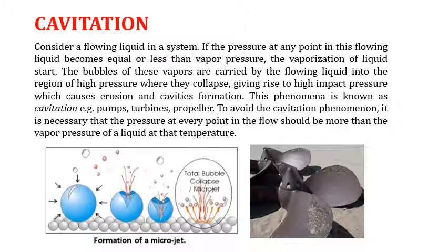and those bubbles are carried by the flowing liquid into the region of high pressure. When they come in contact with the boundary of the pipe, they are going to collapse, and they are going to cause erosion and cavities. This phenomenon is known as cavitation. It is observed in pumps, turbines, propellers.